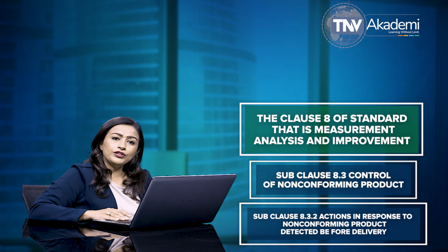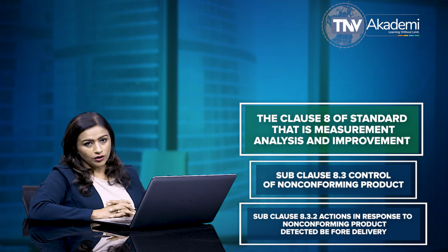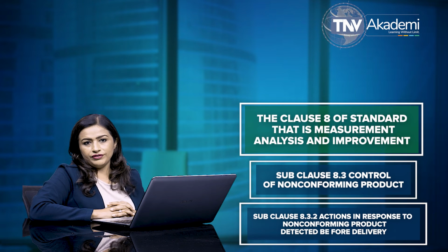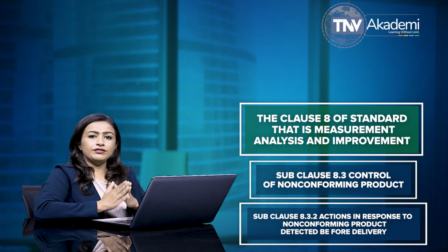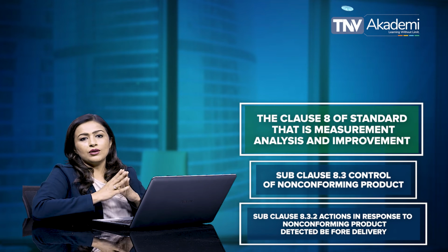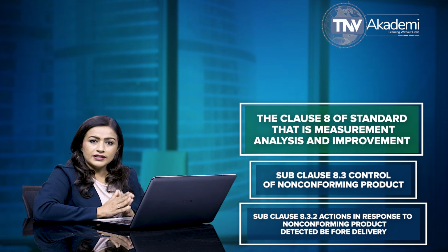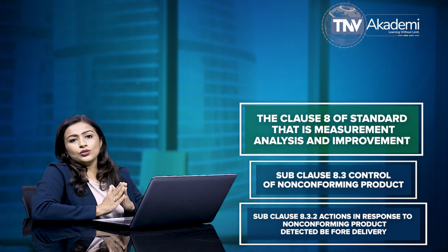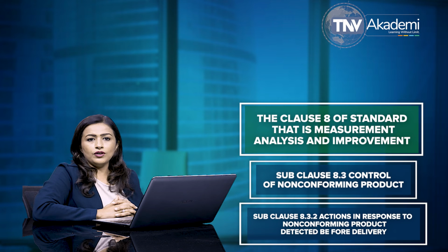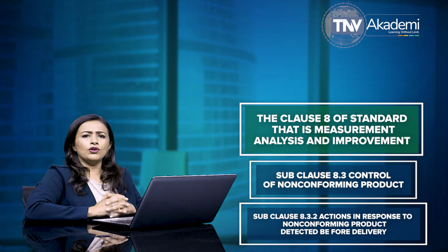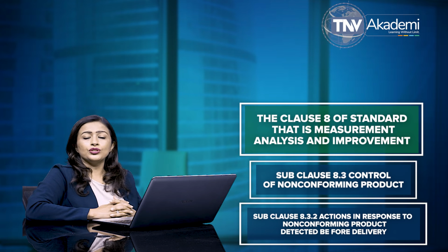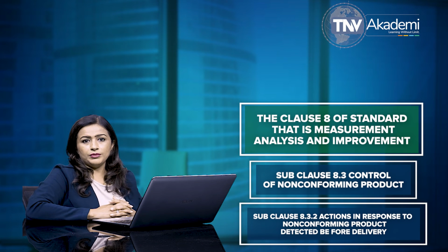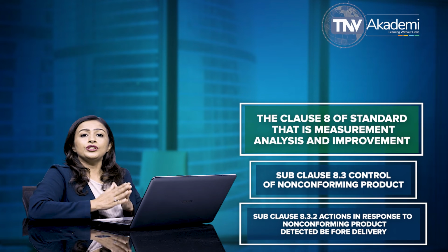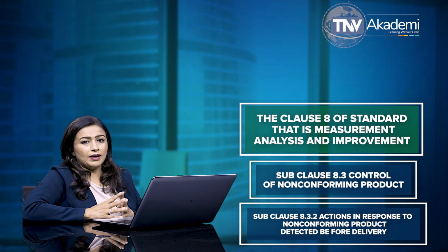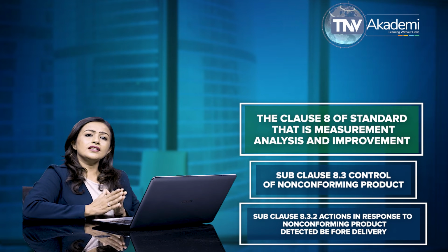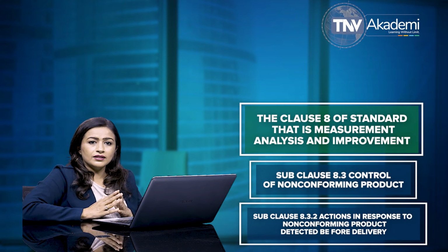Coming to subclause 8.3.2, actions in response to non-conforming product detected before delivery. This subclause 8.3.2 of ISO 13485:2016 states that the organization is required to deal with non-conforming product in one or more of these ways: taking action to eliminate the detected non-conformity, taking action to preclude its original intended use or application, and authorizing its use, release, or acceptance under concession.